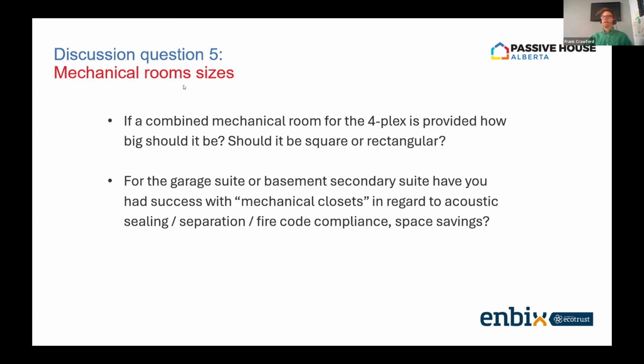Stuart: I would separate the ERV discussion from the domestic water discussion. At this scale, I don't think you're big enough to warrant a central ERV. Four to five suites, you're talking like 1,000 to 1,200 CFM. That's a $15,000 commercial ERV, either a Swegon or Tempeff or something, if you want a high performance unit, versus a bunch of Vanees or Aldes units. On capital cost alone, you're saving money just using an ERV per suite, let alone the extra distribution and fire dampers. Fire dampers have to be inspected every year, so paying for them up front doesn't mean you're done, there's a lot of maintenance cost down the road too. I don't think this is near big enough to consider a central ERV, you'd need to be into 20 plus suites for that capital cost to tip over and for the other things to work out.